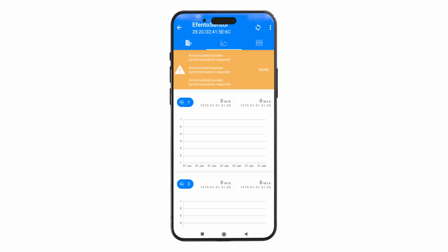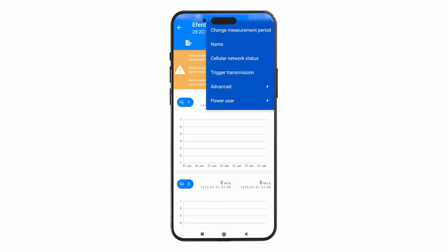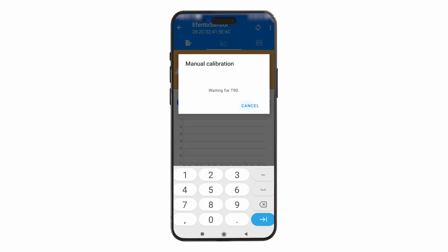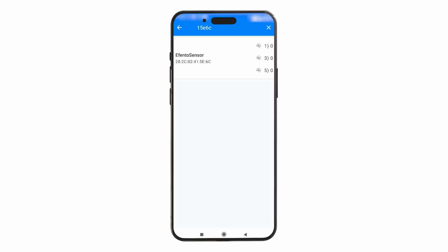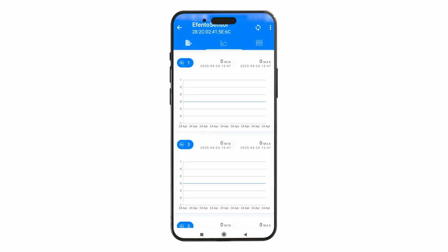Connect to the sensor via the mobile app, open the menu in the top right corner of the screen, and navigate to Advanced, Calibration, and then Manual Calibration. Select the channel you wish to calibrate, enter the initial value, and confirm the change. This process must be done individually for each of the 3 channels. After successfully completing the manual calibration, return to the list of nearby devices and wait for 1 measurement period. The calibration notification will disappear, and the initial values for the respective channels will be displayed on the right side.